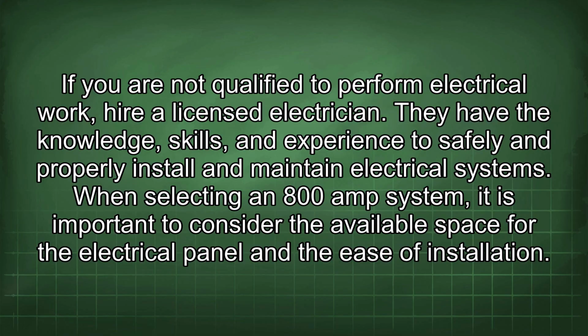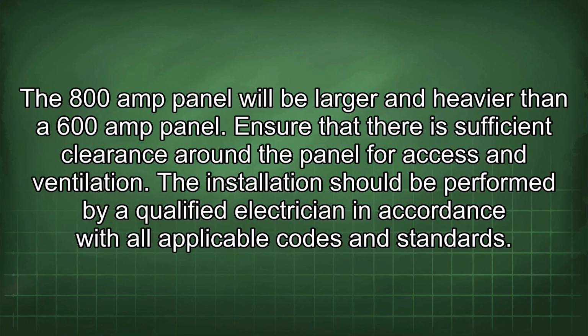When selecting an 800 amp system, it is important to consider the available space for the electrical panel and the ease of installation. The 800 amp panel will be larger and heavier than a 600 amp panel. Ensure that there is sufficient clearance around the panel for access and ventilation. The installation should be performed by a qualified electrician in accordance with all applicable codes and standards.